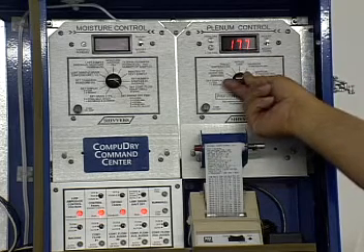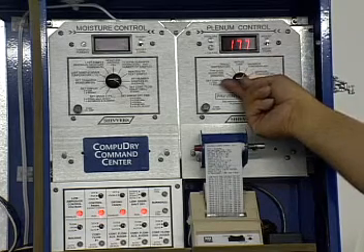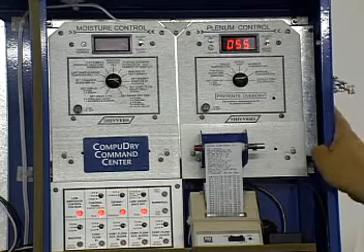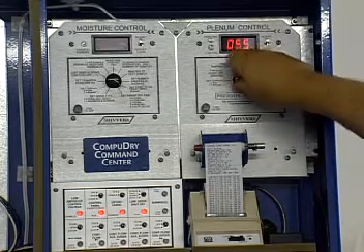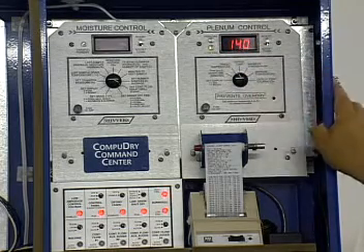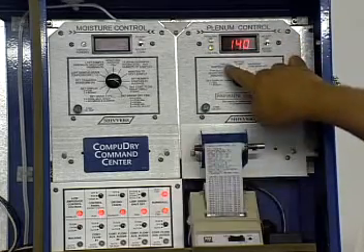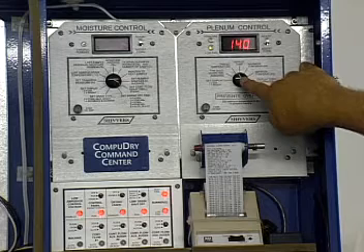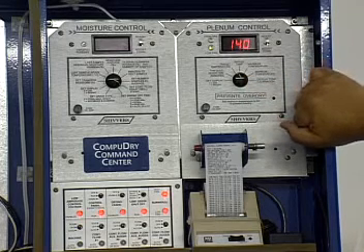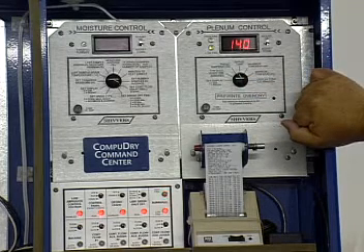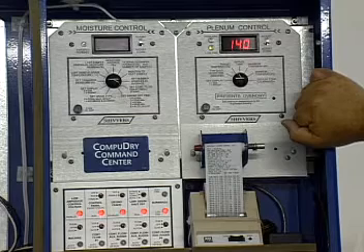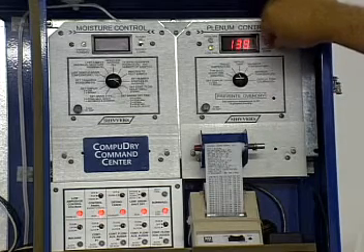We've got our maximum set in here at 177. We got our minimum set in here at 55. And we've got a target temperature here of 140. Now the burners have fired. Remember, target temperature is the temperature that the computer wants to run at based on the moisture sample it got. Right now the moisture control is not running. We're just pre-drying. So I can set this however I want to set it.